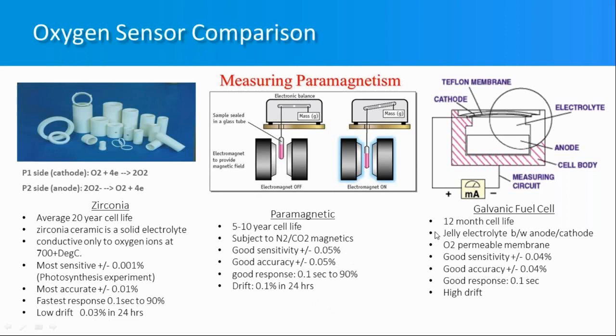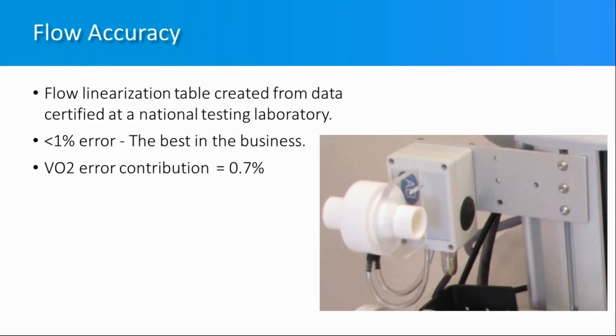Flow is really important as a parameter. The Moxis metabolic cart has a very low flow error of around 1% on average, and its contribution to VO2 error is quite low as well.